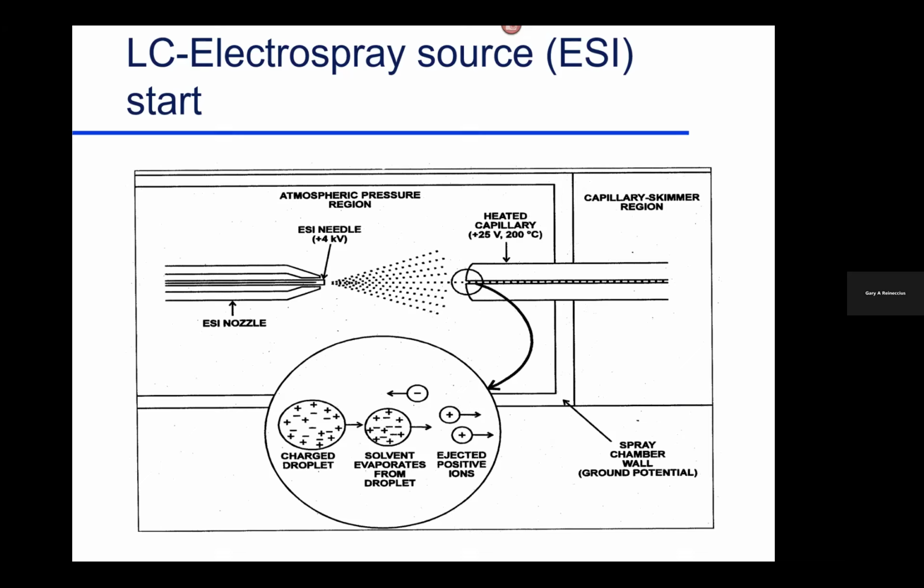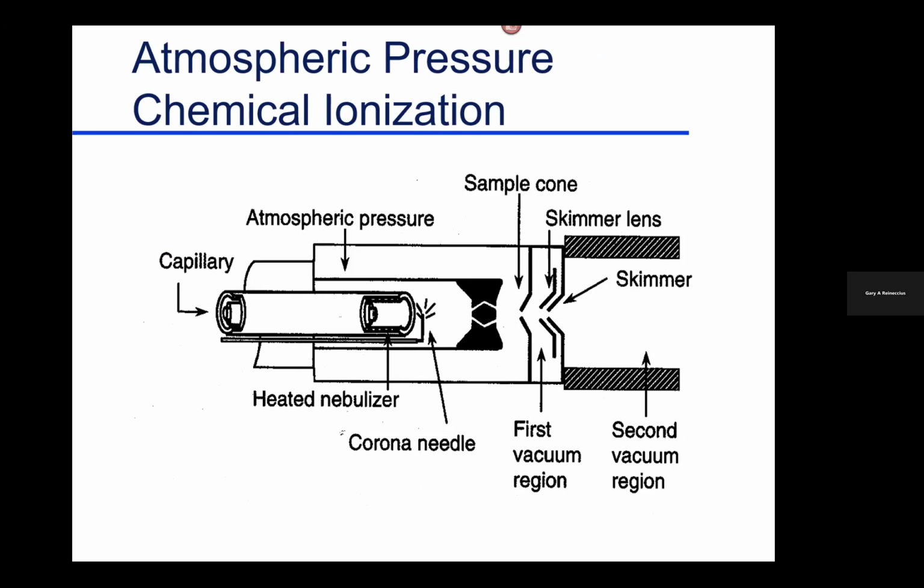And that solvent tends to evaporate, leaving ions behind, or the molecules from the sample you're analyzing. Your sample comes in that side and hits this electron-dense area, which makes things evaporate in the process. So that's how we separate our liquid carrier from ions. Like I say, that's the most common. There are other ways to separate our sample from the liquid coming out of the HPLC.